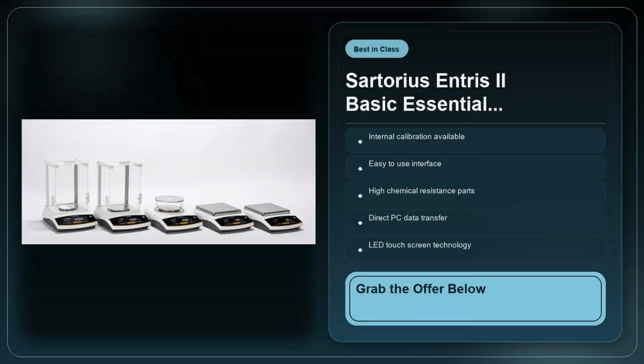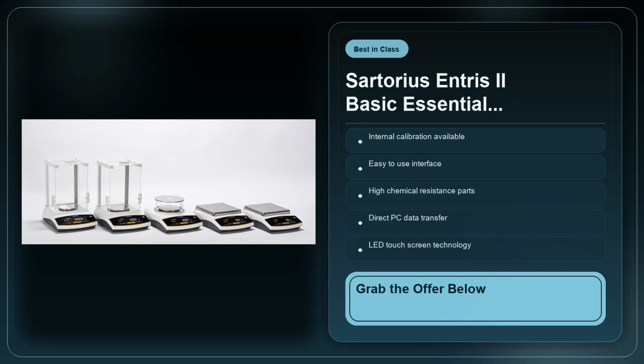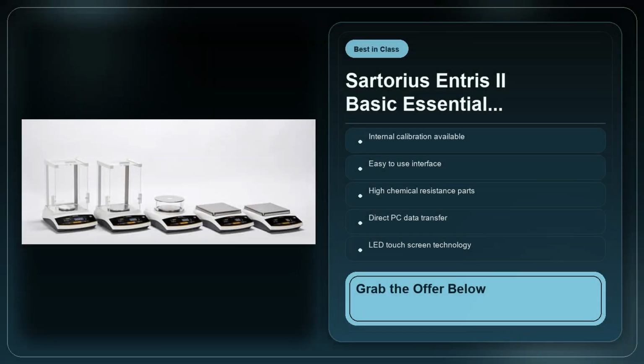On the flip side, if you're working in a high-throughput environment where you need to weigh up to several kilograms per sample, or you need ultra-high precision below 0.01 mg for trace analysis, the Entris II Basic may feel cramped. The 60 g limit caps the size of the samples, and while 0.1 mg readability is solid for many applications, it isn't enough for the most demanding microanalysis work. Also, the optional data cable is an extra purchase. It's not bundled, so if you need that connectivity right out of the box, you'll have to budget a little extra. There are a couple of practical weaknesses worth mentioning.